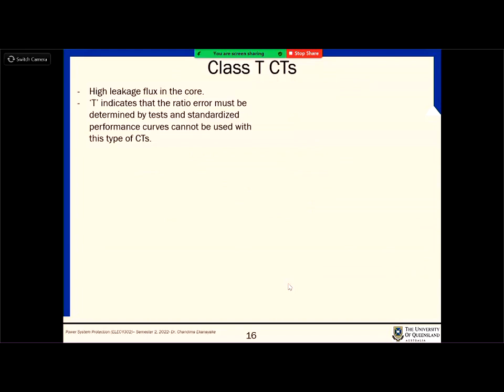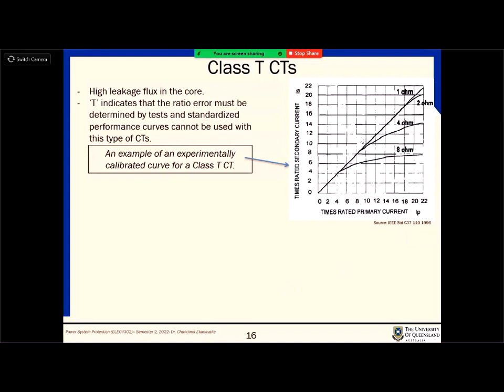So when I mentioned these two classes, you have Class T and Class C. For Class T CTs, the error has to be determined by a test. You can't just define that all these old Class T CTs have this much error under these conditions. No way. You need to do a specific standardized test to define this curve, so you have to do the test yourself. An example is given here. Why these 1 ohm, 2 ohm, 4 ohm, 8 ohm, what does that mean? These are the burdens.